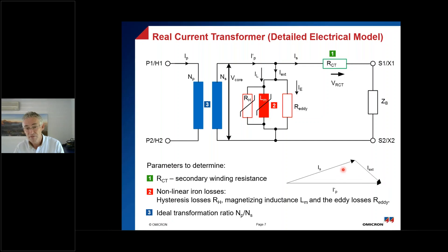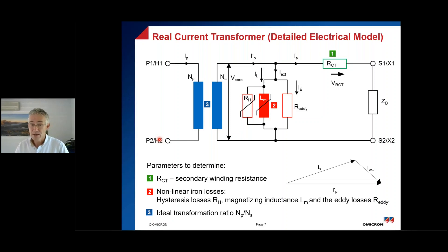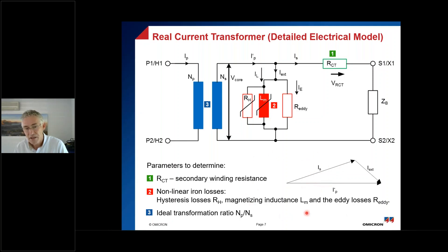From the vector diagram we see two important effects: first, IS is always smaller than IP in magnitude, meaning a CT will always have a negative amplitude error — it outputs slightly less current than the ideal primary current. Second, IS leads the transformed primary current IP', meaning a CT always shows a positive phase angle error. This is consistent with what we observe in measurements, and both effects will be confirmed in the case studies.